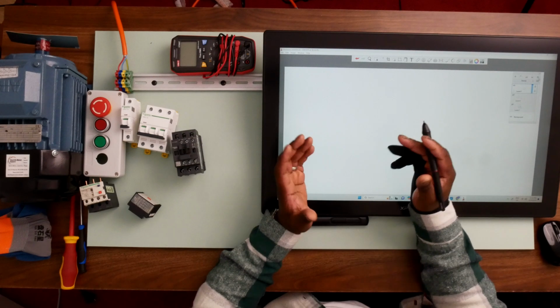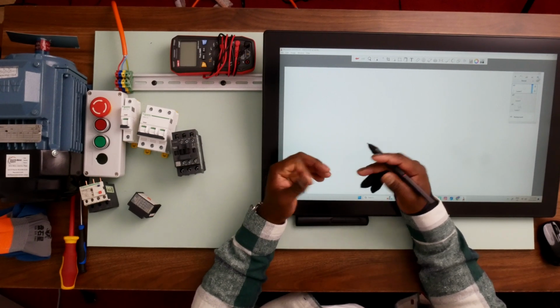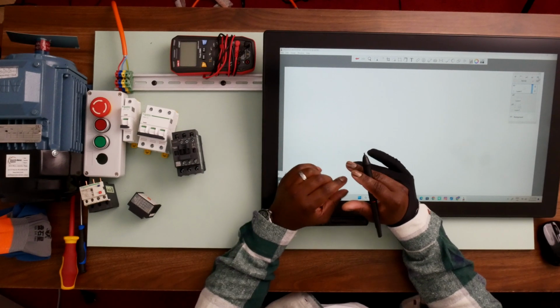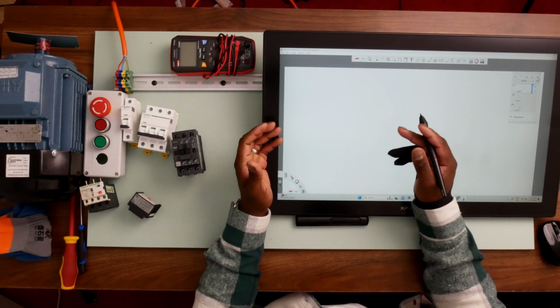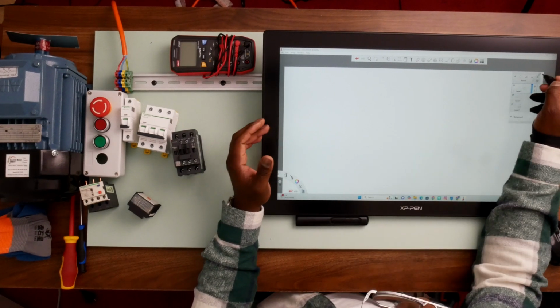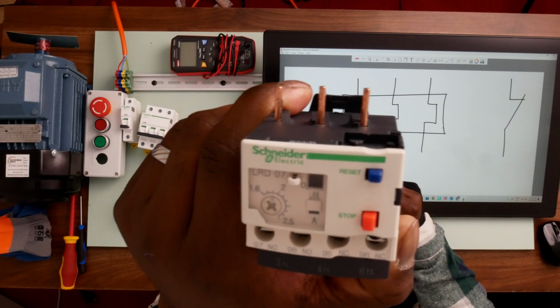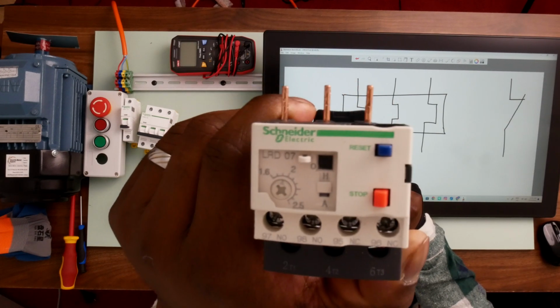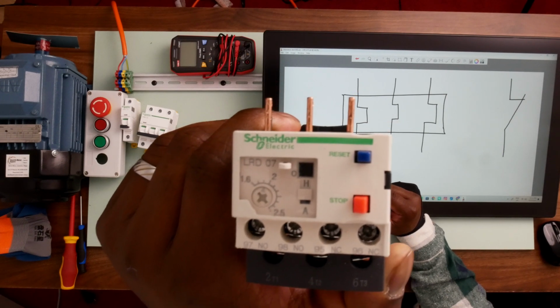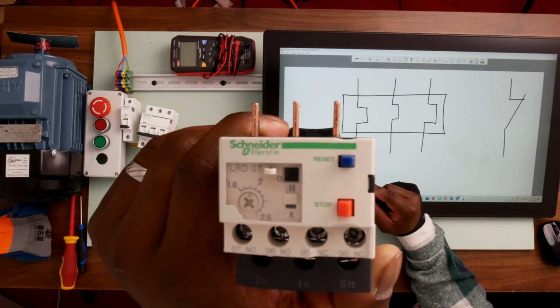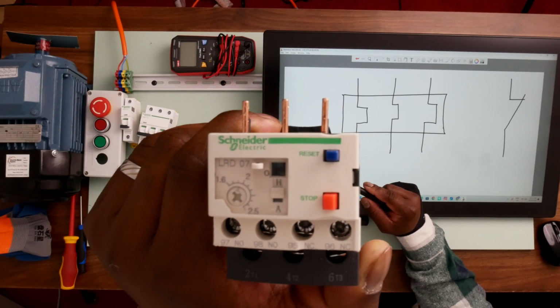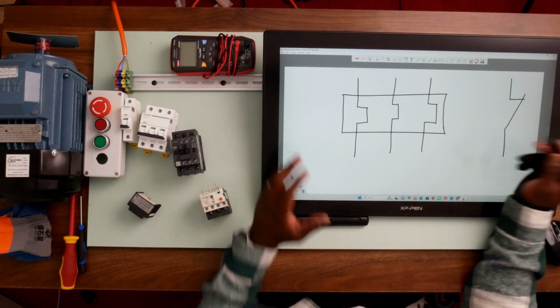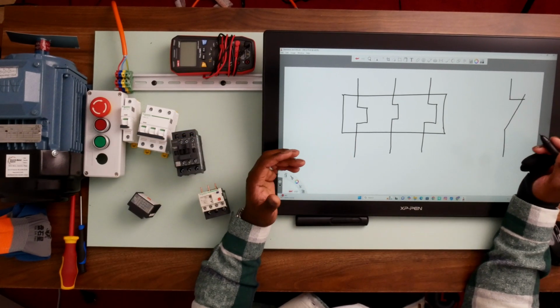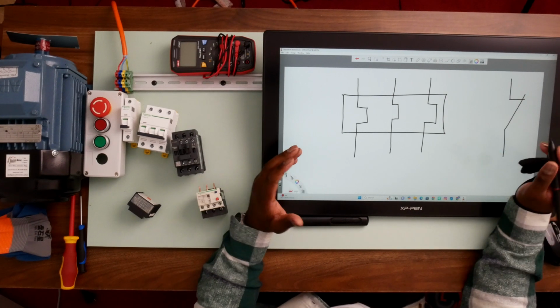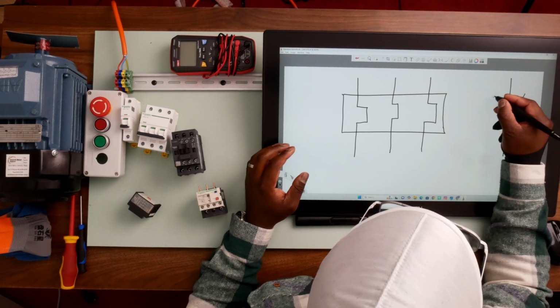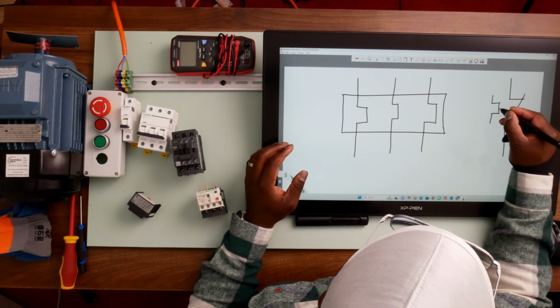The next component that we are going to discuss here is the overload relay. Just like the contactor, the overload relay is part of both the power circuit and the control circuit. The symbol for the overload relay is like this. On the overload relay, there's a normally open contact, which is 97 and 98, and a normally closed contact, 95 and 96. For this control circuit, we are only interested in the normally closed contact, which is 95 and 96. So for the symbol here, we're not going to bother drawing the normally open contact because we don't need it for this exercise. We just need the normally closed contact. So this is the control circuit symbol for the overload relay.